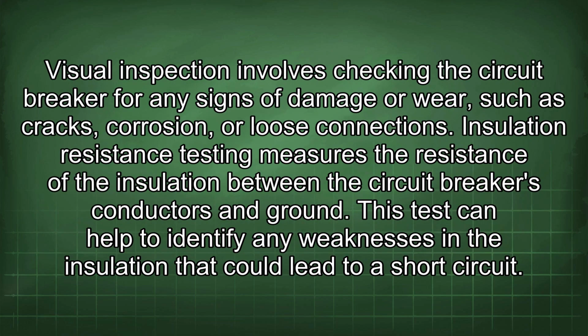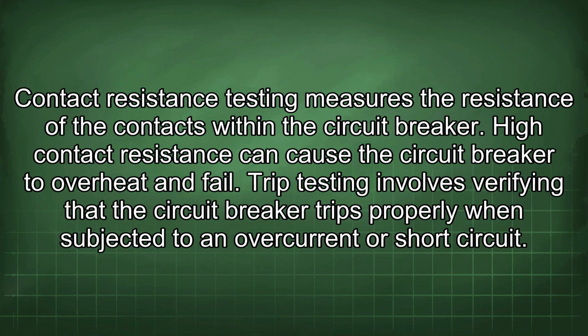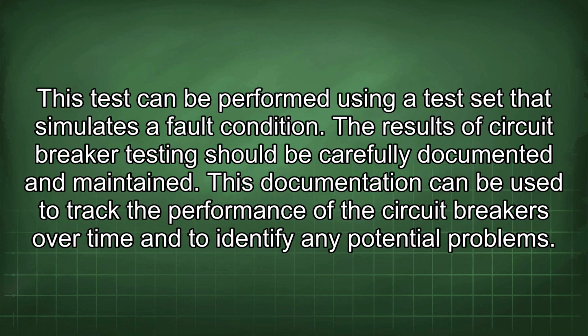Visual inspection involves checking the circuit breaker for any signs of damage or wear, such as cracks, corrosion, or loose connections. Insulation resistance testing measures the resistance of the insulation between the circuit breaker's conductors and ground. This test can help to identify any weaknesses in the insulation that could lead to a short circuit. Contact resistance testing measures the resistance of the contacts within the circuit breaker. High contact resistance can cause the circuit breaker to overheat and fail. Trip testing involves verifying that the circuit breaker trips properly when subjected to an overcurrent or short circuit. This test can be performed using a test set that simulates a fault condition.